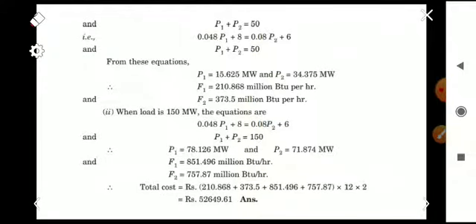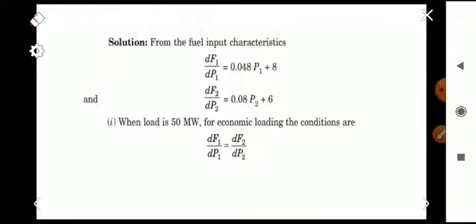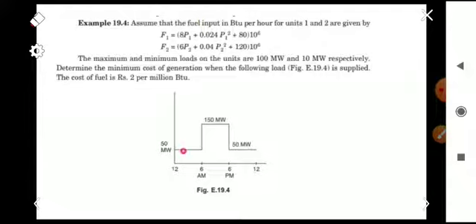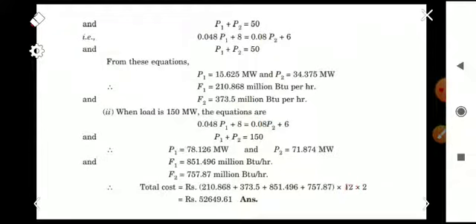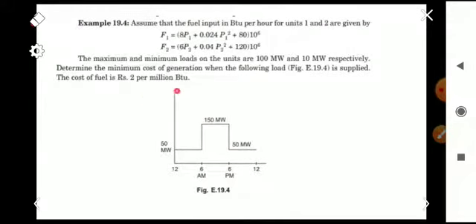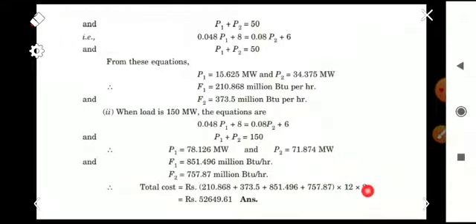Since both loads — 50 megawatt and 150 megawatt — each run for 12 hours, we multiply the total hourly fuel cost by 12. We also multiply by 2, because the cost of fuel is rupees 2 per million BTU. So the total cost is (F1 + F2 for 50 MW + F1 + F2 for 150 MW) × 12 × 2, giving a total cost of rupees 52,649.61.